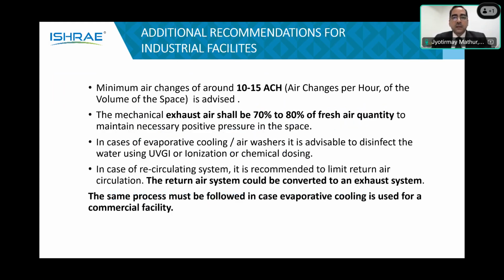Coming to other facilities, in industrial facilities we recommended a higher air change, 10 to 15 air changes, compared to the lower air change in commercial buildings, because industrial applications have the possibility of higher air change, so we asked why not go for that. We suggested that it's better if the exhaust air is 70 to 80% of the air supply, so that you can easily bring in fresh air.